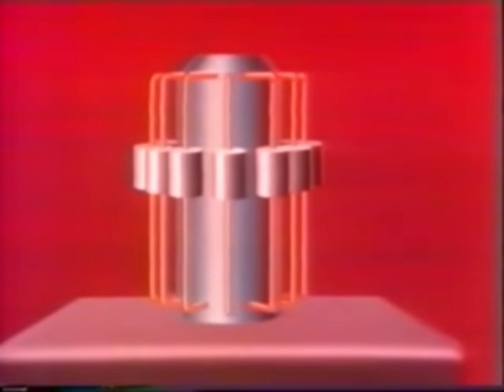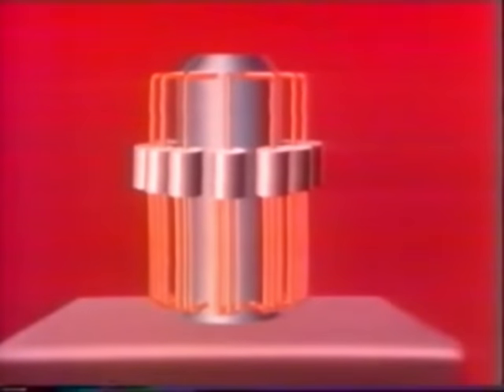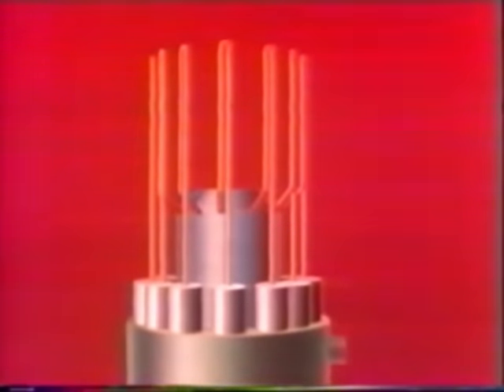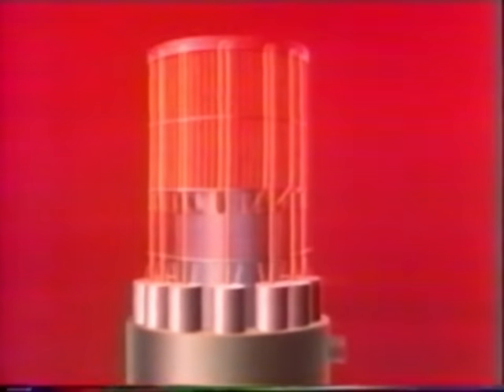Efficient cooling is ensured by subdividing every cooler tube into many smaller ones. All these are embedded in the cooler housing through which water is pumped. The heater is improved by extending the heater tubes, increasing their number and adding fins. The exact dimensions of the heat transfer system result from a thorough investigation of the Stirling cycle and have been evaluated electronically to minimize the sum of all the losses.